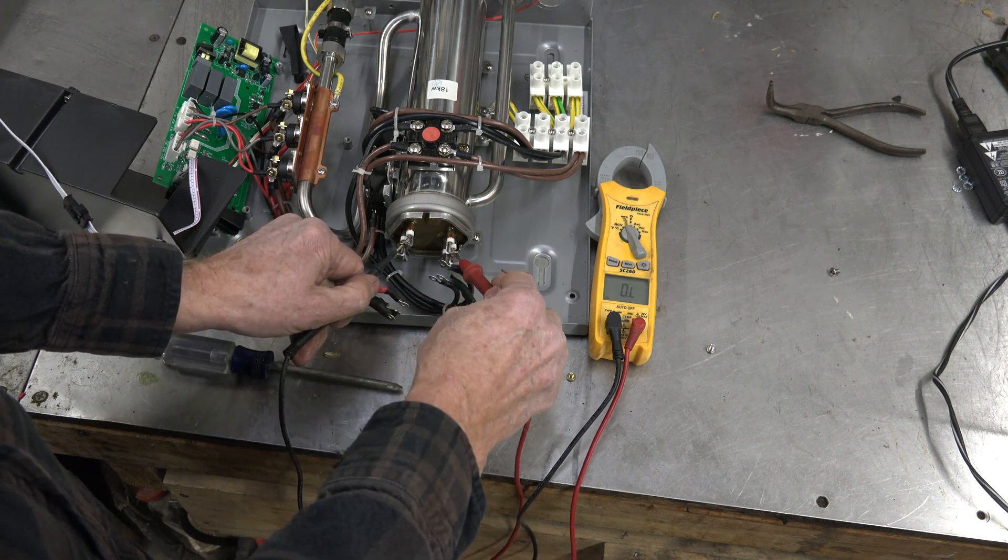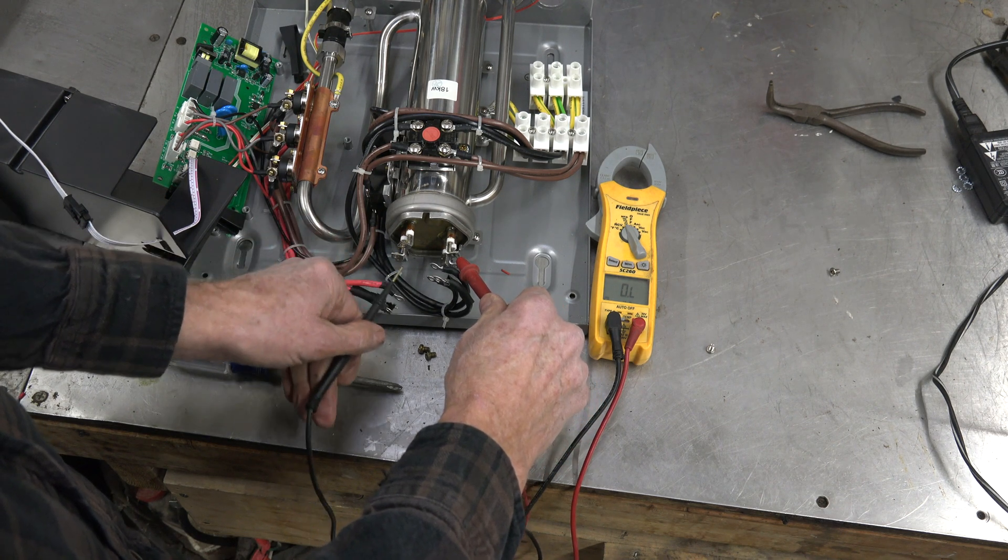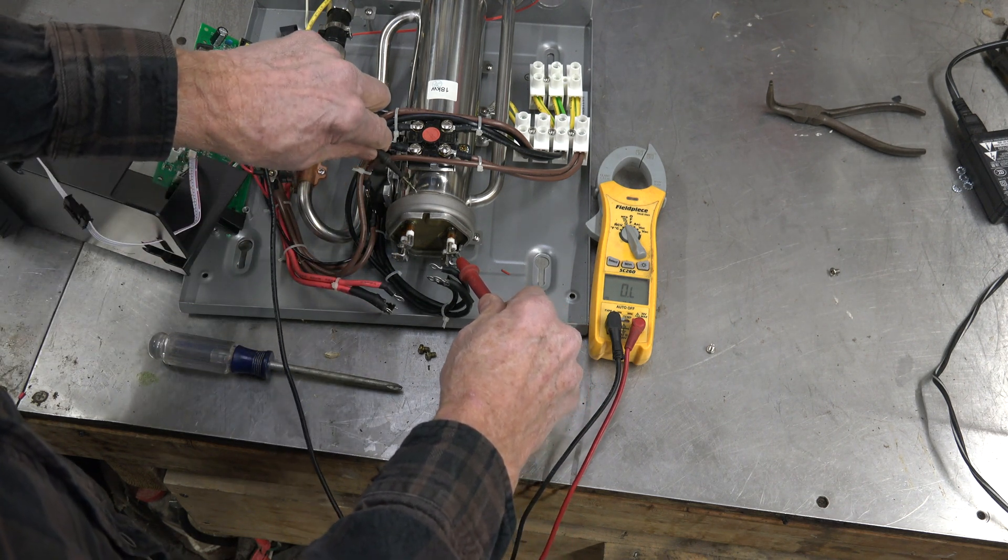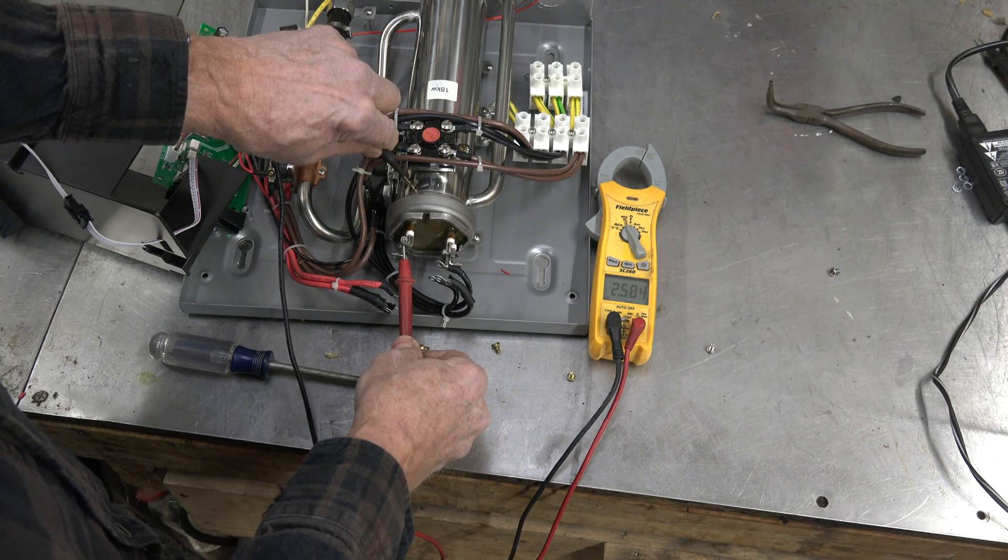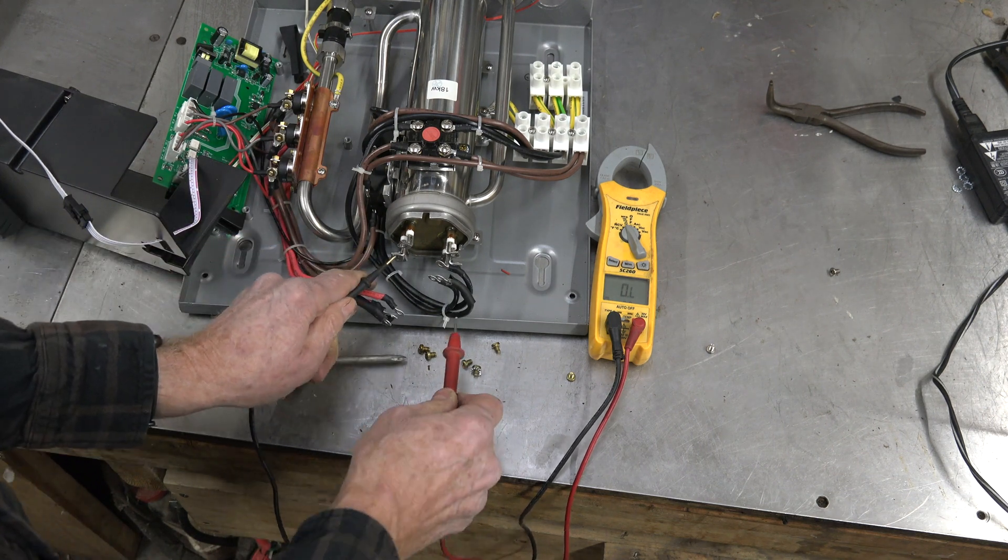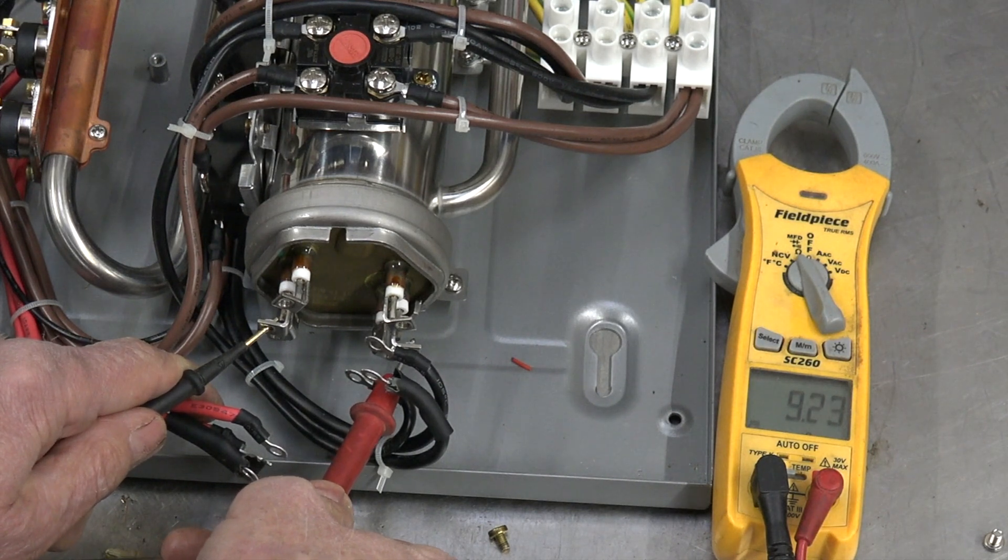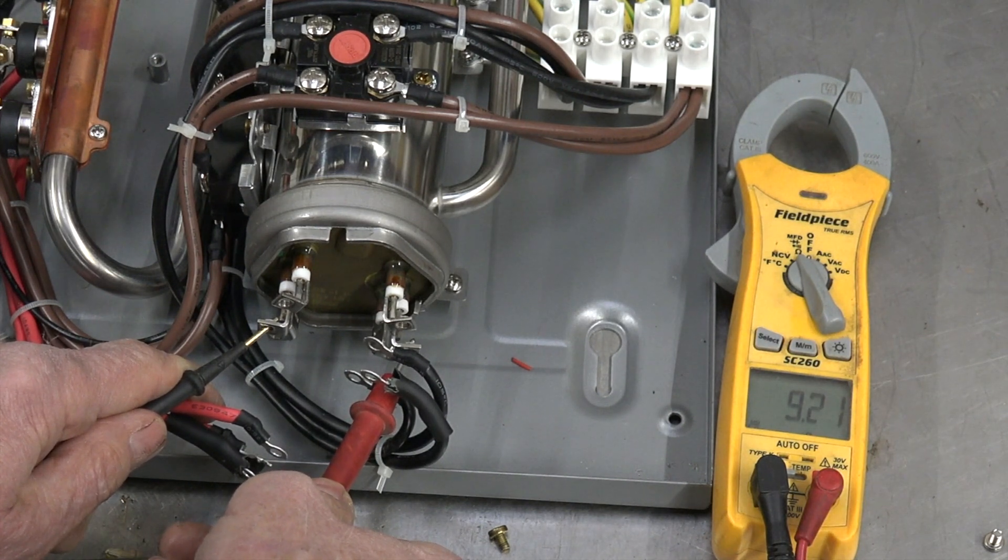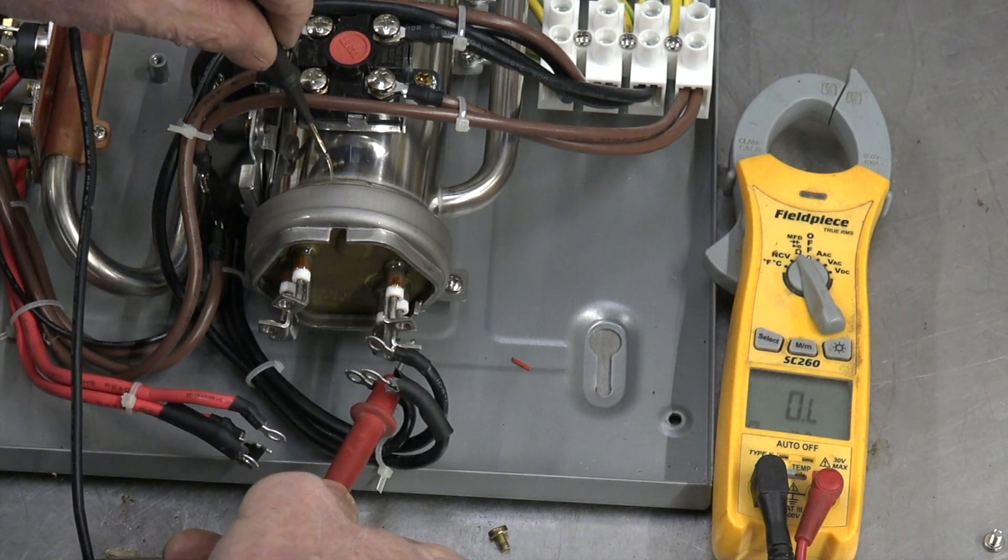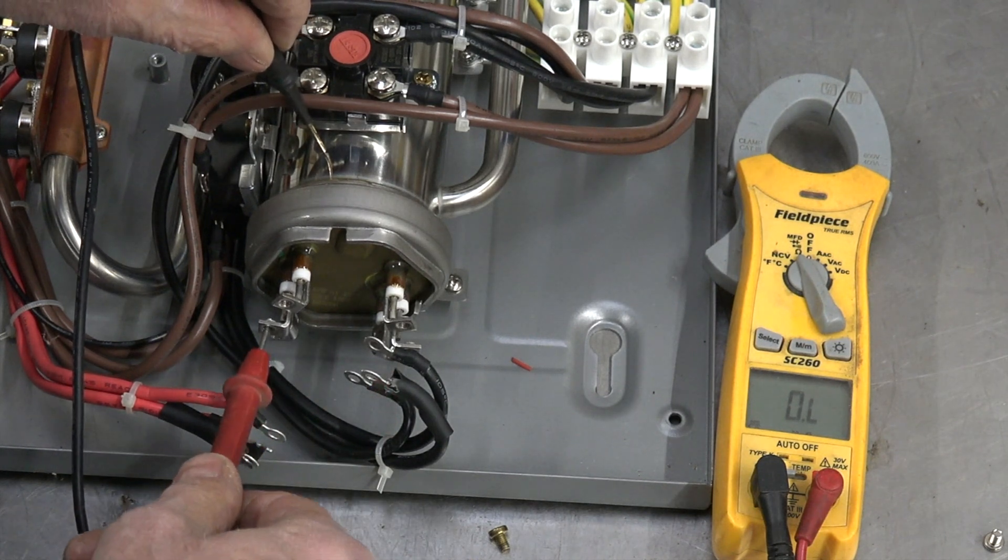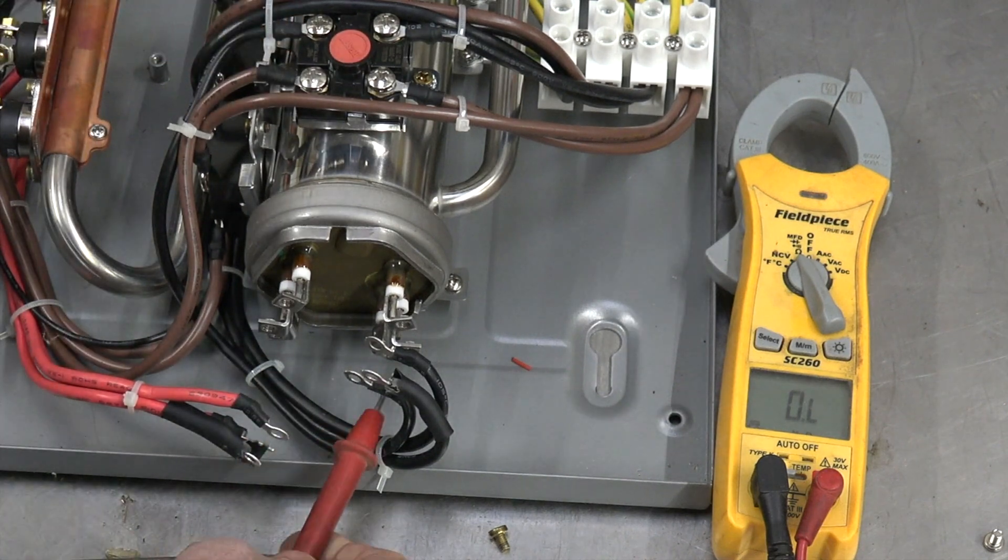Let's go a little further. We'll double-check this one again. This one is OL between the two terminals, OL on this side, and has resistance on that side. Center element: now that's 9.19 ohms - that's ohms, not kilohms. Let's go to ground: no continuity. Go over here: no continuity. So that element's good.